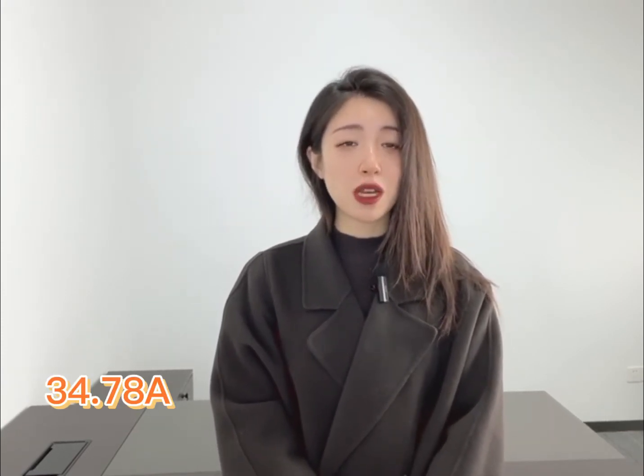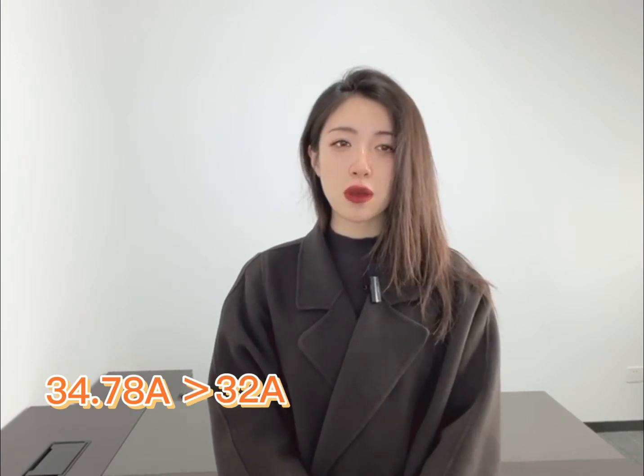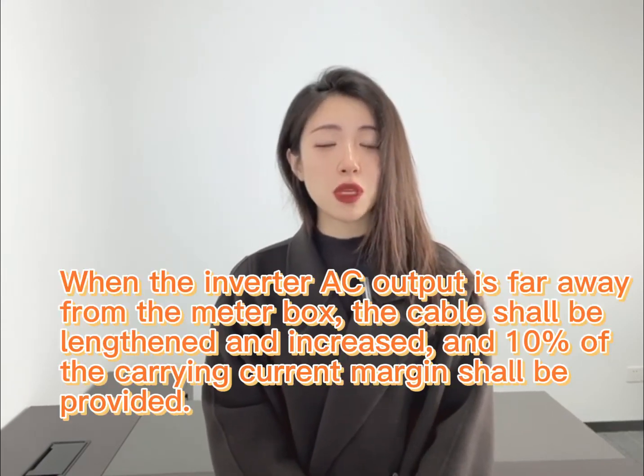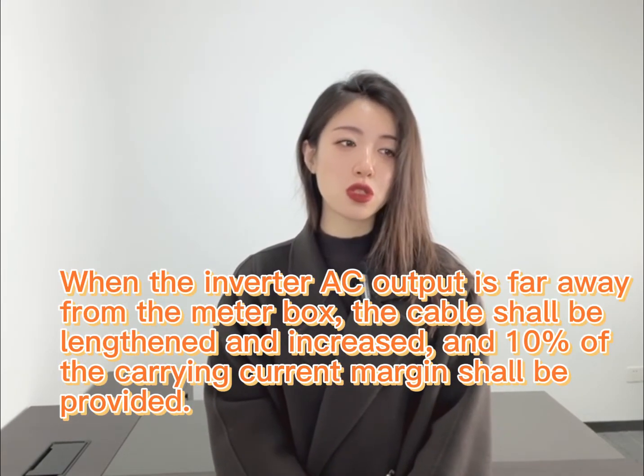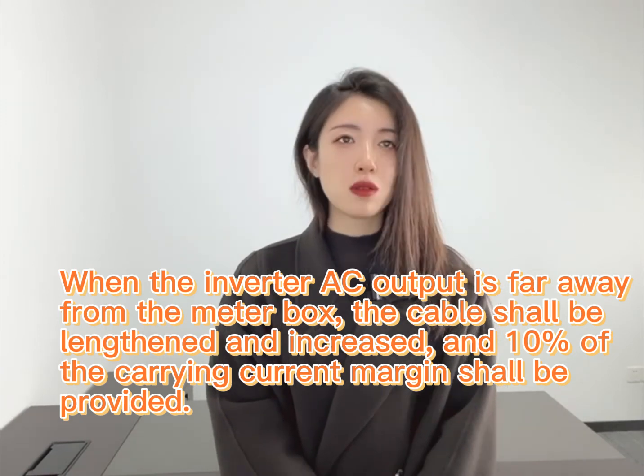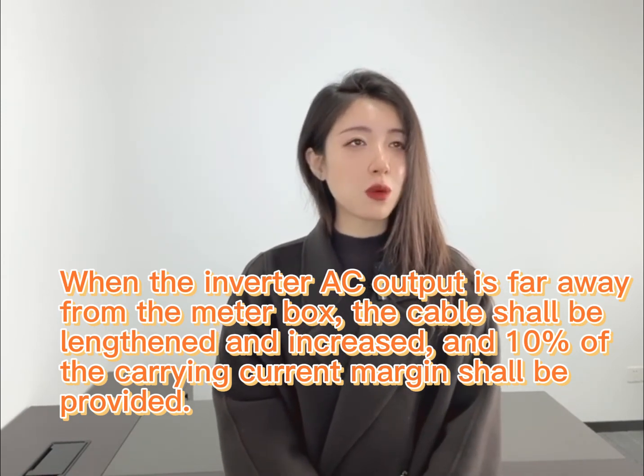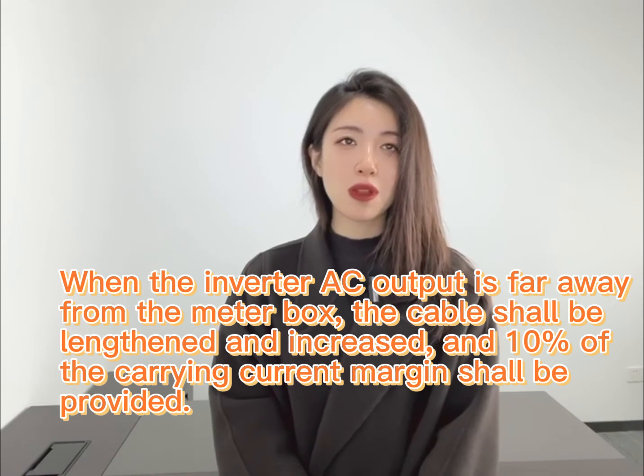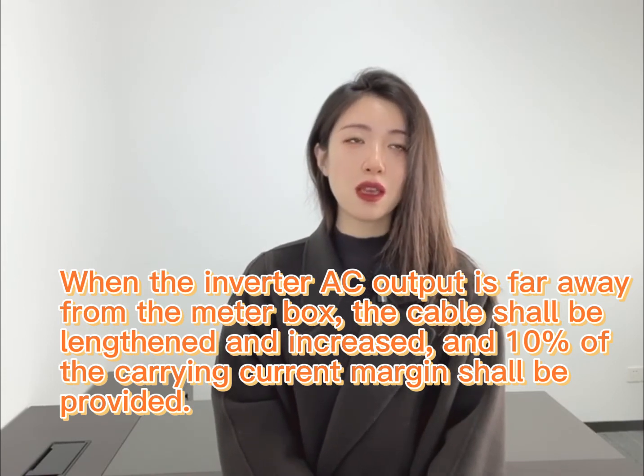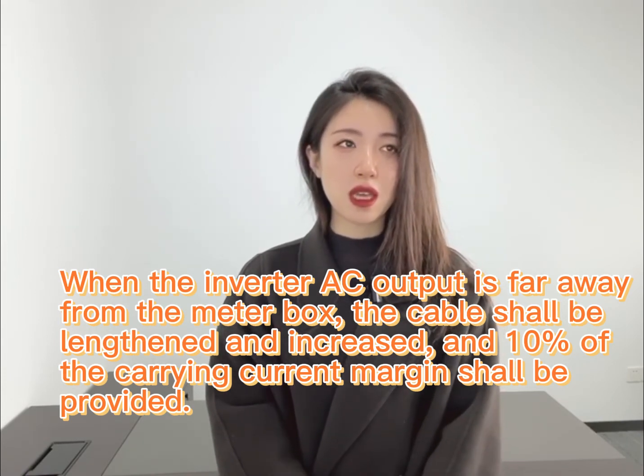If a single-phase 8 kilowatt machine has a maximum output current of 34.78 amperes, but you choose a 32 ampere switch, your AC breaker will frequently trip off at noon in the summer, when the peak output power is easily reached, because the current is too high. When the inverter AC output is far away from the meter box, the cable shall be lengthened or increased, and a 10% carrying current margin shall be provided.